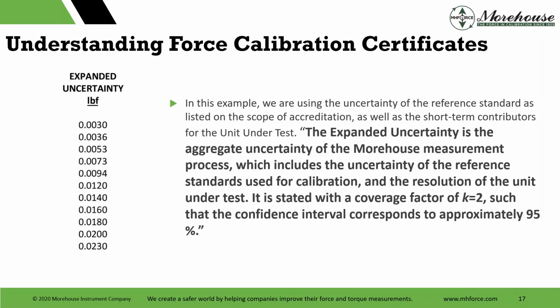In this example, we're using the uncertainty of the reference standard listed on the scope. And here's what we were saying. The expanded uncertainty is the aggregate uncertainty of the Morehouse measurement process. That's what we did for our CMC uncertainty parameter, the Morehouse measurement process, which includes the uncertainty of the reference standard used for force calibration and the resolution of the unit under test. So we've done our repeatability studies, we've done everything else. What we're adding here is what we know, which is the resolution. That has definitely changed and is definitely one of our short-term contributors. And the resolution of the unit under test is stated with a coverage factor of k equals 2 such that the confidence interval corresponds to approximately 95%.